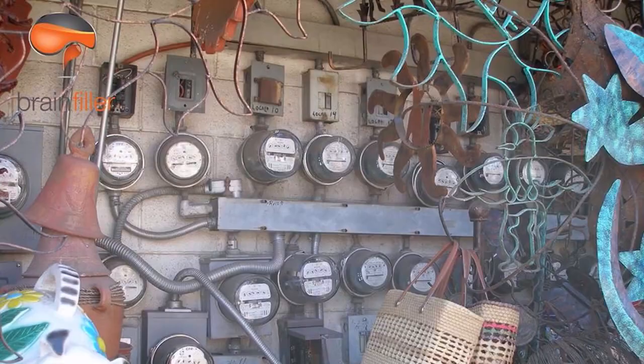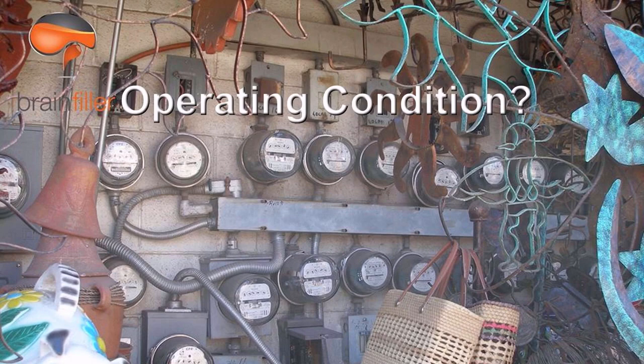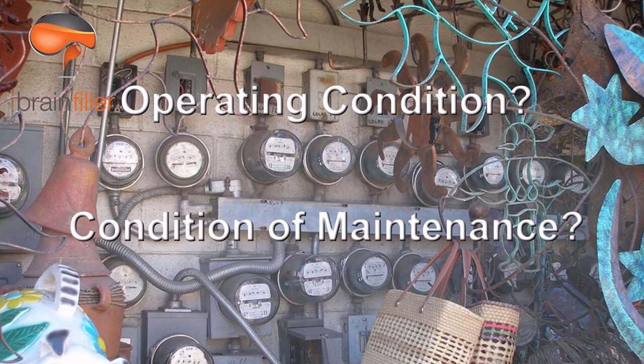But let's look at this. So we have item number two, the condition of maintenance of the equipment. Well, okay. I actually took this photograph years ago, and if you were to try to make a judgment about the operating condition or a judgment about the condition of maintenance, I don't know. I don't think that would work out too well. So, you know, there's a lot that goes into this when you're trying to evaluate: is there a shock hazard? Is there an arc flash hazard? I mean, for the shock hazard, if you look at this close enough, you'll see a few covers removed and things like that. I don't know if it's energized, but you don't know. I do have to give them credit for creative conduit routing. They made a very effective use of flex conduit for this one.